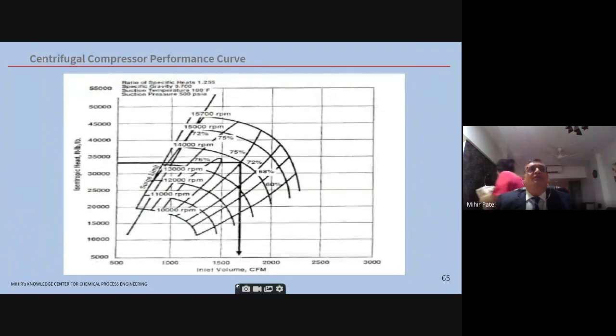Now the centrifugal compressor performance curve. This is pretty similar to a centrifugal pump performance curve. As can be seen, on the left-hand side is the head, on the x-axis is the volume, and you have the different speeds. So RPM speeds are there. The performance curve is there, and the surge limit is there on the left. Best efficiency point also you have to see where it falls into.